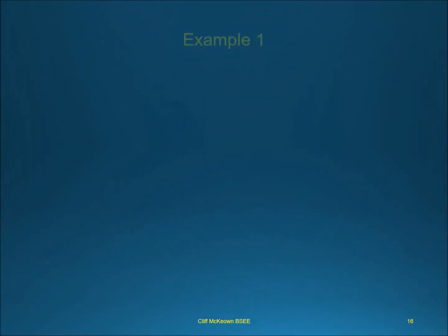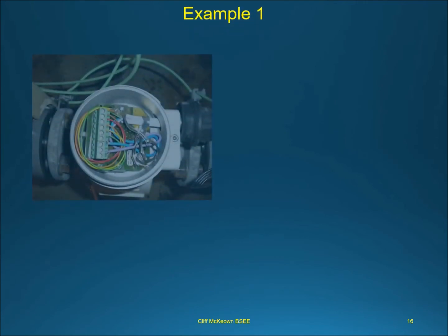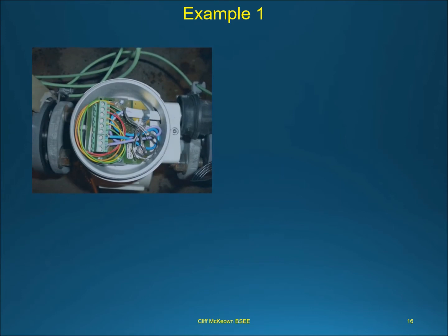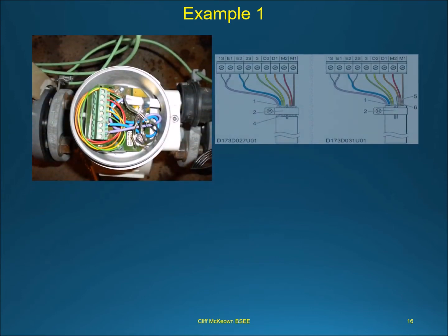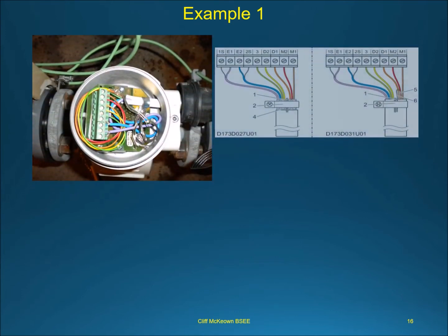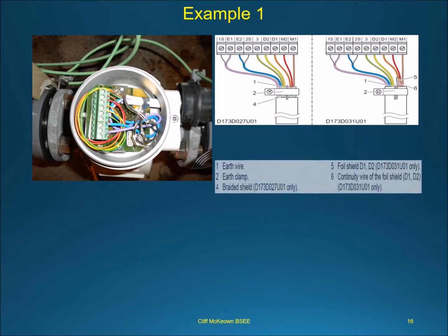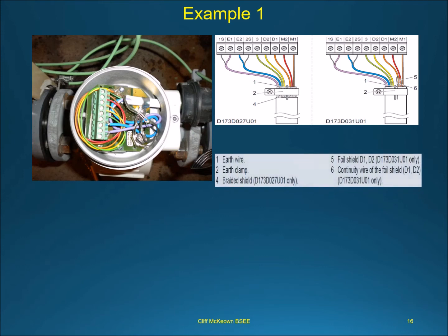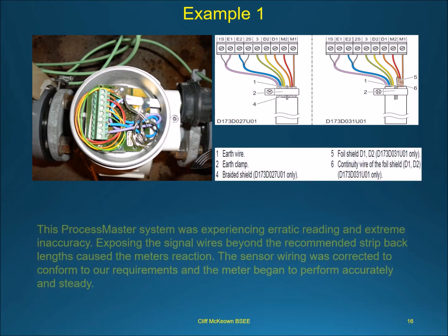Example 1. This Process Master system was experiencing erratic readings and extreme inaccuracy. Exposing the signal wires beyond the recommended strip-back lengths caused the meter's reaction. The sensor wiring was corrected to conform to our requirements and the meter began to perform accurately and steadily.